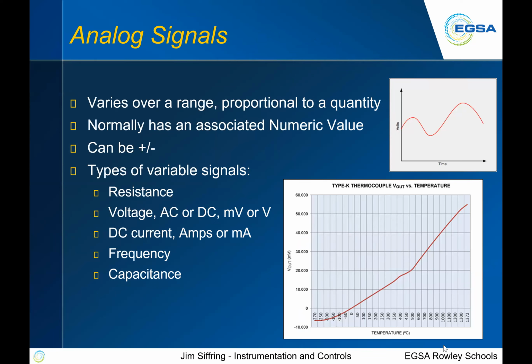So as we bring up analog now, what is analog? Analog is a signal that varies over a range. It's proportional to some quantity of some kind. If you look in the lower right, the thermocouple versus temperature chart, as temperature goes up, the voltage out of that device goes up. So it's proportional. Generally speaking, it's a fairly smooth line, but you can chart all those things. It can be positive. It could be negative. It could actually come from the upper left and go to the lower right.